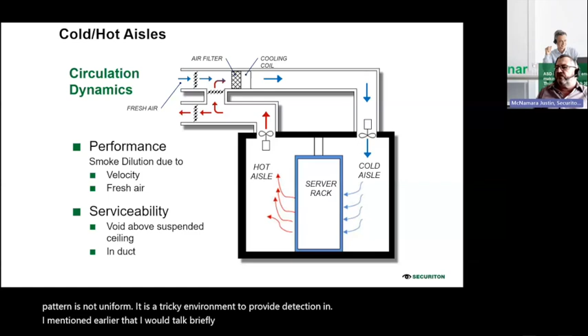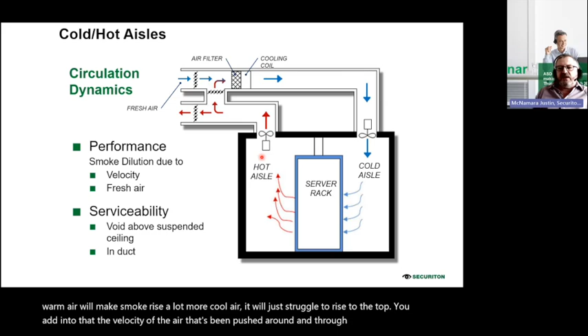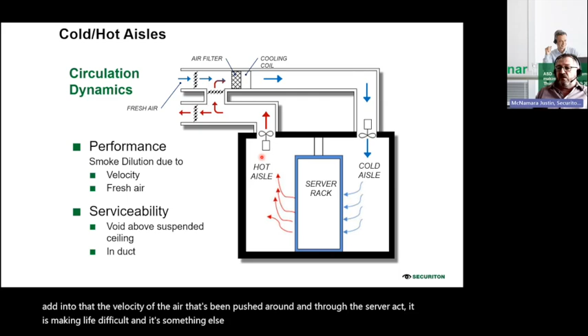I mentioned earlier that I would talk briefly about the difference between hot and cold aisles. This is one example. On the left-hand side we have the hot aisle, which is warm air being pushed out from the server rack. Behind it, on the other side, is where the cool air comes in from the room cooling system. Smoke will behave very differently in a cool aisle versus a hot aisle. Warm air will make smoke rise a lot more, while cool air will struggle to rise to the top. Add in the velocity of the air being pushed around and through the server rack, and it makes life difficult, something else we need to be aware of.